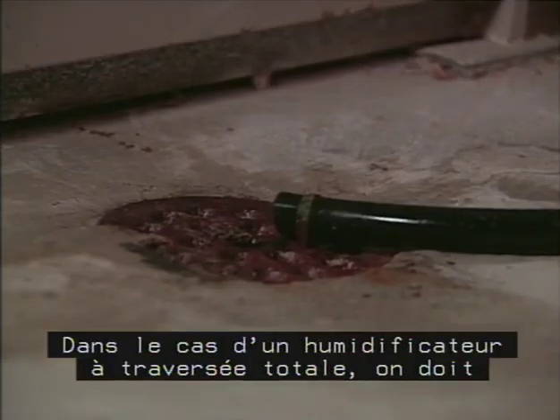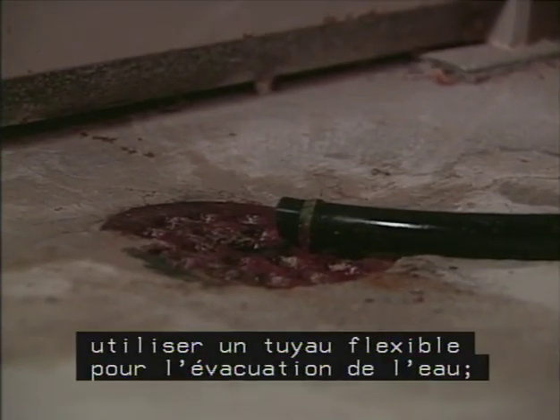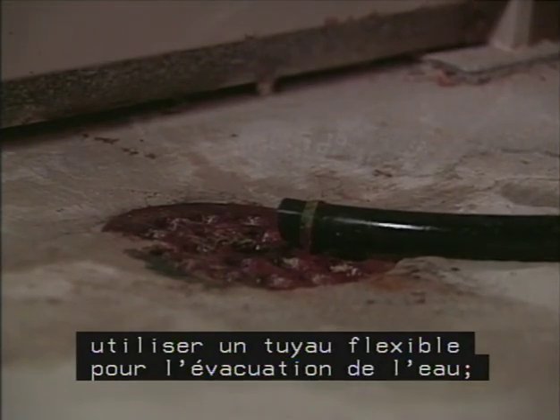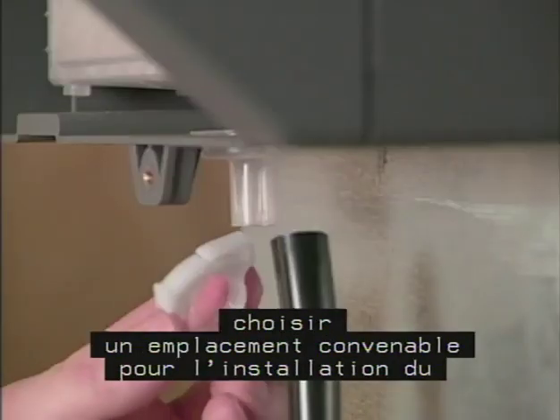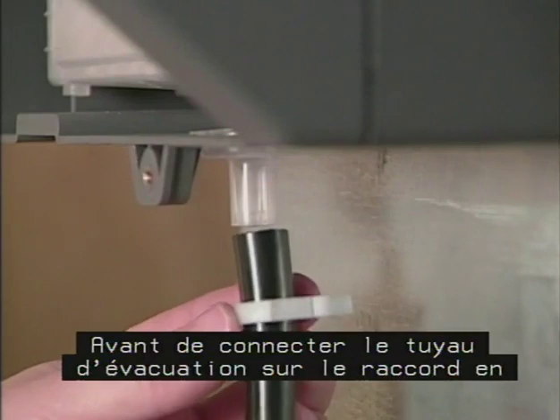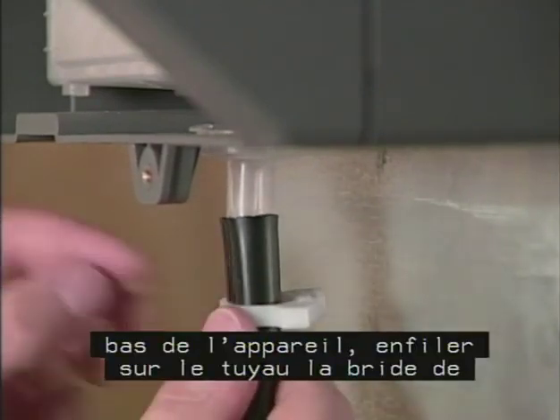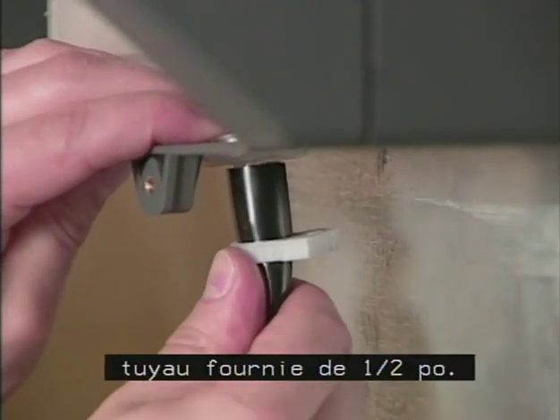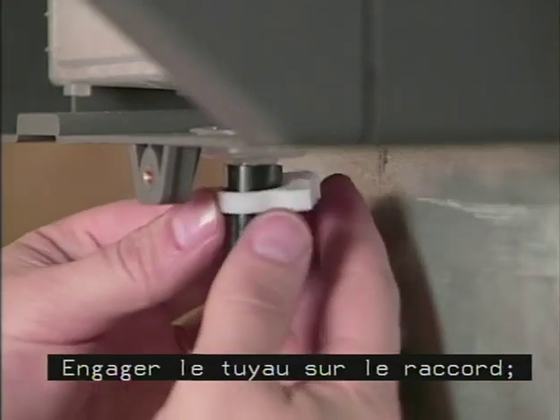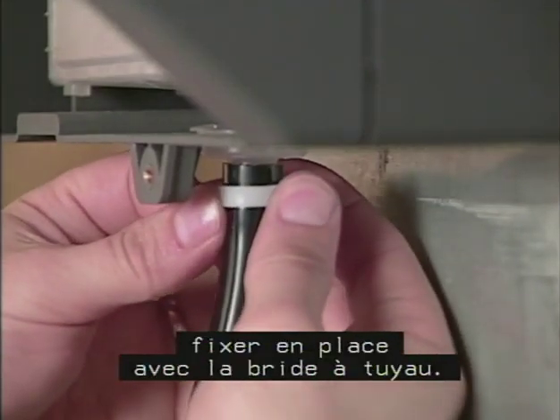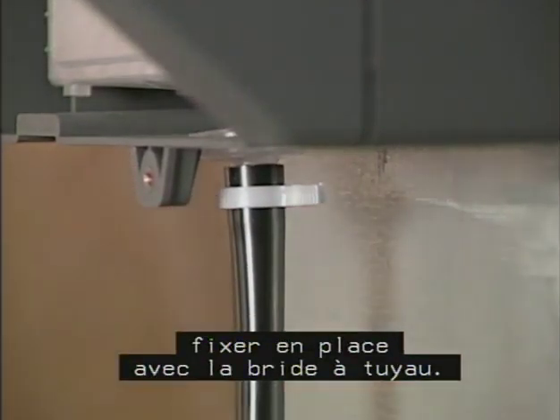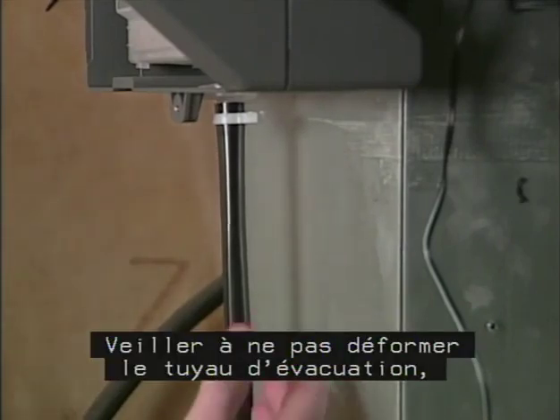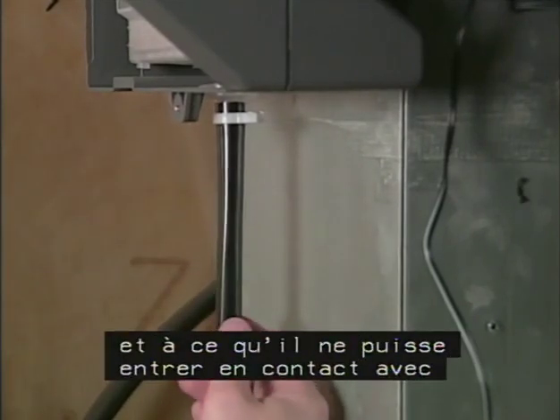A drainage tube must be used with all flow-through humidifiers, so select a convenient location for running the half-inch drainage tube. Before you connect the tubing to the drain fitting on the bottom of the unit, slip the supplied half-inch hose clamp over the tubing. Push the tubing over the fitting and secure it in place with the hose clamp. Take care that the drain tubing does not kink or come into contact with sharp edges or hot surfaces.